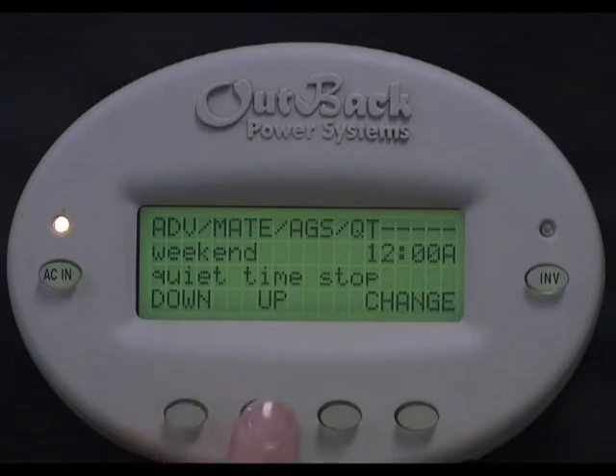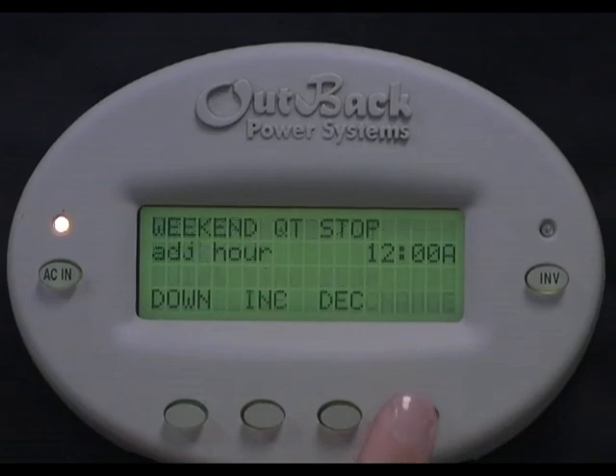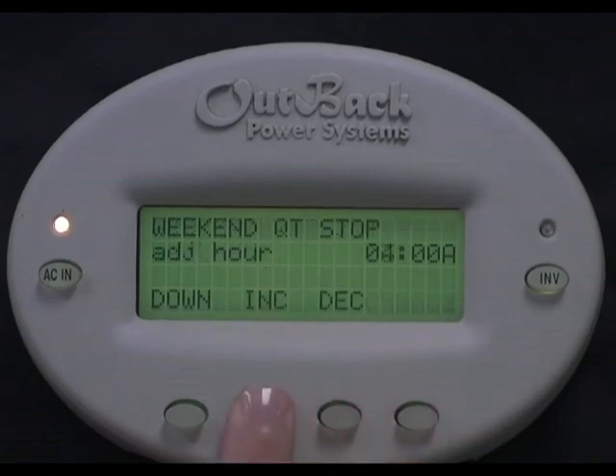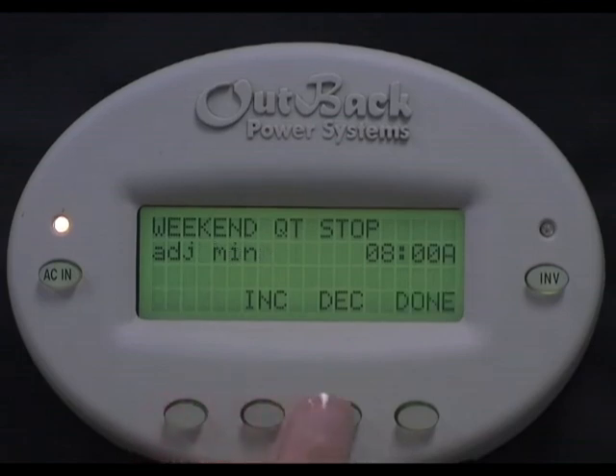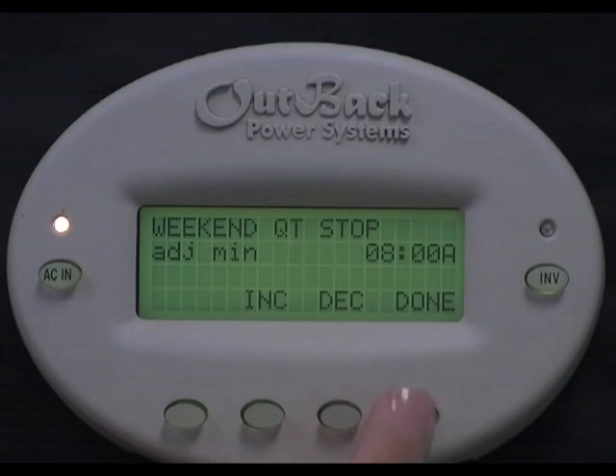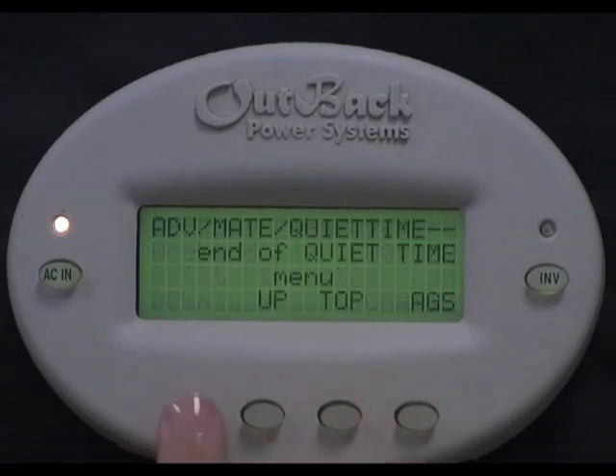Weekend Quiet Time Stop is the stop of the time period when you don't want the generator to run Saturday and Sunday. So in our 10pm to 8am example, this time would be set for 8am. To set it, select Change, then Increase or Decrease to adjust the hour. Select Down, then Increase or Decrease to adjust the minutes. Select Done, then select Down.